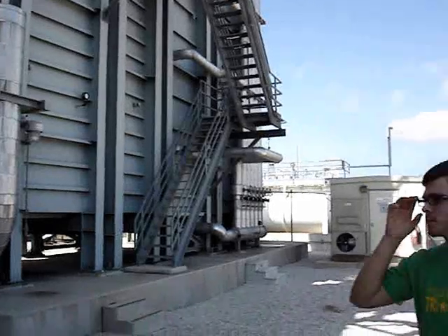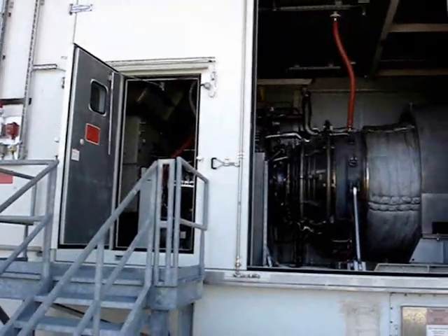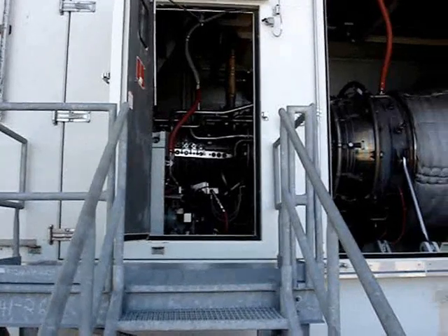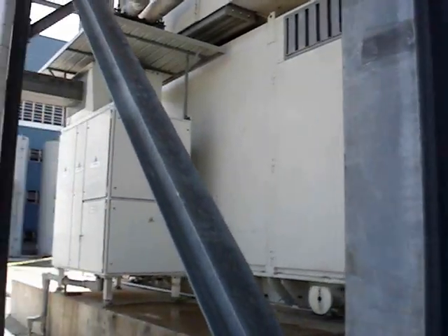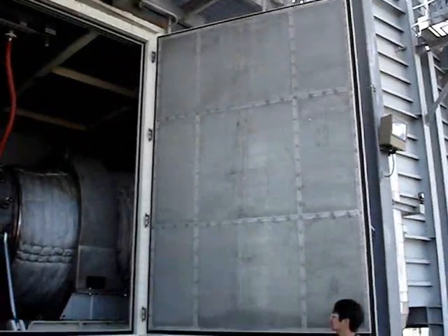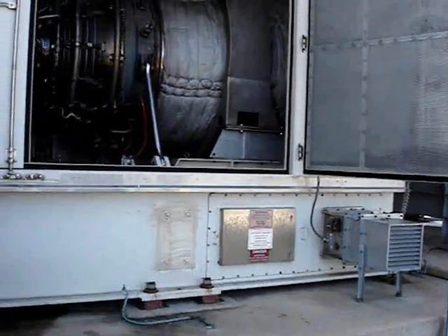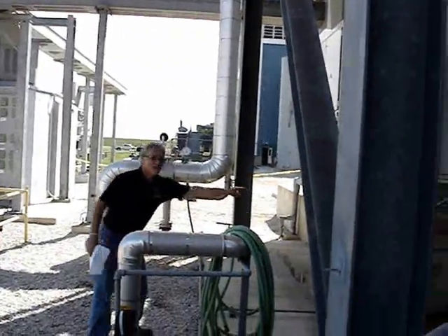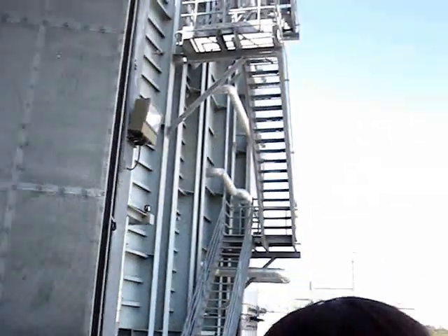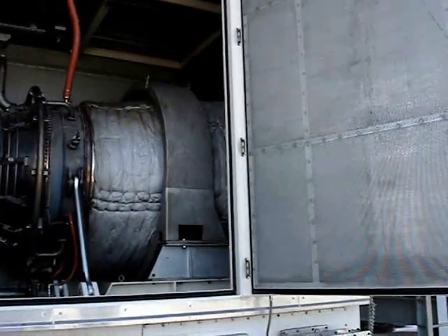Units 2 and 3 are General Electric LM6000 Aero Derivative Combustion Gas Turbines, which generate a range of 49 megawatts. The combustion cores are jet engine derivatives of GE's CF6-80C2 aircraft engines, which are currently used on Boeing 747, Boeing 767, McDonnell Douglas MD-11, and Airbus A300 aircraft. NASB-2 was constructed in 2003, NASB-3 in 2009. Everything from that slab to that corner is jet engines — that is the engine itself. What you see going up this way is called the SCR, or Selective Catalytic Reduction. You have the stack on the end, and on that side over here you have the actual generator.